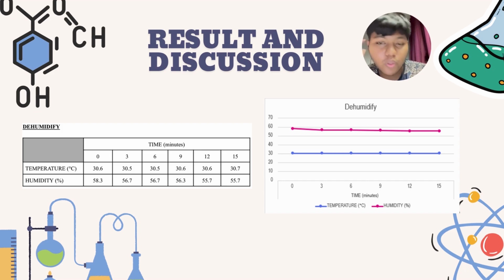So lastly, we're going to be looking at the last part of our experiment, which is the dehumidifying process. Looking at our temperature data, we can see that our temperature actually remains constant, between 30.5 degrees Celsius and 30.7 degrees Celsius. This indicates that heat removal is minimal and well balanced during the moisture removal. For the humidity data, we can see that our humidity decreases from 58.3% to 55.7%.